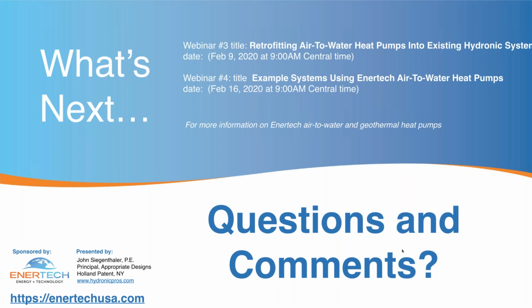And Jim or Jeff, if you're on, I don't know if you want to comment on that at all. Okay. Yeah, John, it's Jim. We're about at half capacity at minus 13. And then of course our COP, depending upon the water temperature we're delivering, in most cases we're still above, around 2 or a little bit above. So at minus 13, that's still pretty respectable. Those numbers increase significantly when we get up into the single digits above 0. So it's definitely built for cold winter climate operation. What's another question, Carly?